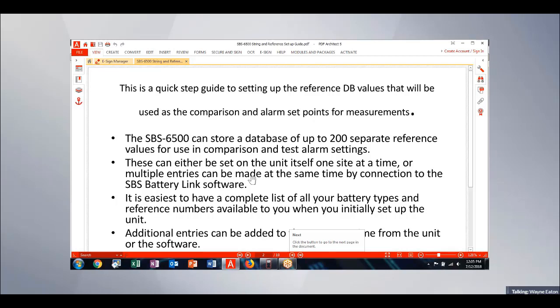They can be set up on the unit itself one by one, but it's much easier to connect the unit to the software and enter all my database references all at one time. And then the software updates all that back onto the unit as you make those changes. So if you've got a complete list of all of your different battery types and manufacturers available to you before you start using the 6500, it makes the entire process a lot easier. One of the other nice things that we did about the unit is that you can go back and modify or update any of those entries over the life of the unit as well.